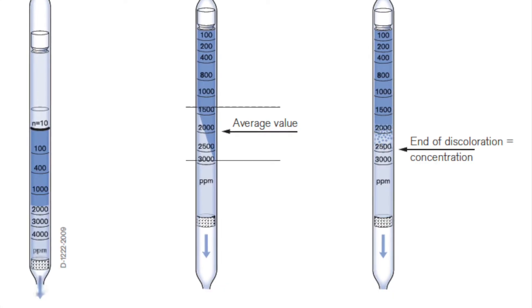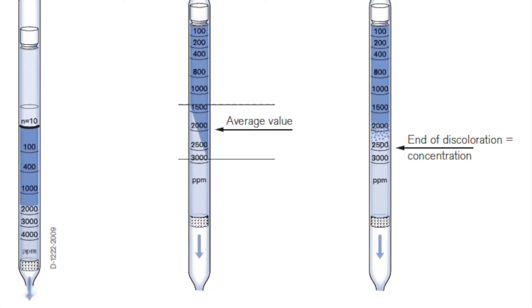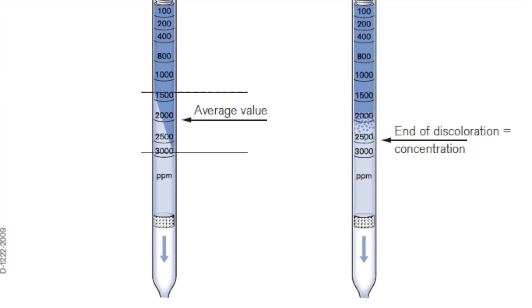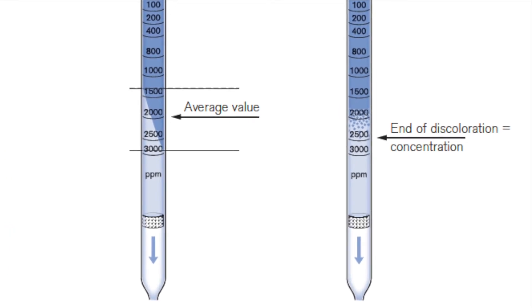If the reddish-brown color change stops in a straight line, you'll write down your closest estimation between the two nearest marks on the tube. If the color change is angled, you'll take the reading exactly in the middle of the angled discoloration. And if the color indication is diffused, take the reading from the end of the diffusion.